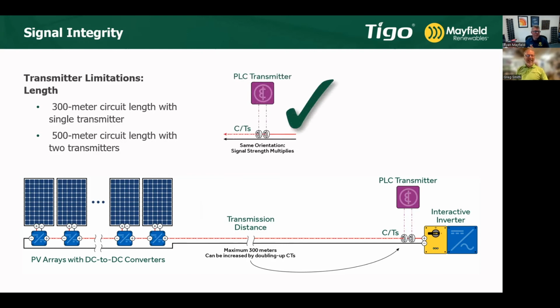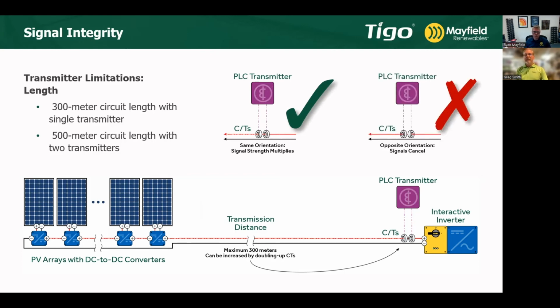Okay, so PLC transmitter, something we talked about as we were prepping for this: make sure your CTs are facing the same direction. They're a directional item, and if you put them in opposite directions, they're going to cancel each other out. You're not going to get 500 meters, you're going to get 0 meters. It's probably an easier mistake to make than people give credit for. Relatively easy thing to fix, but still something you have to fix.